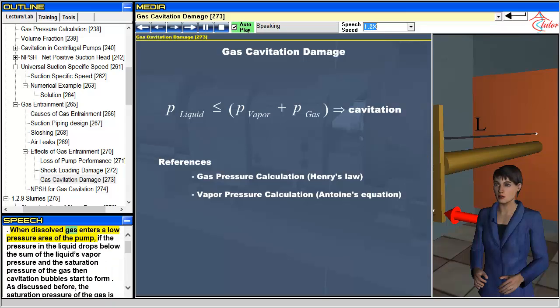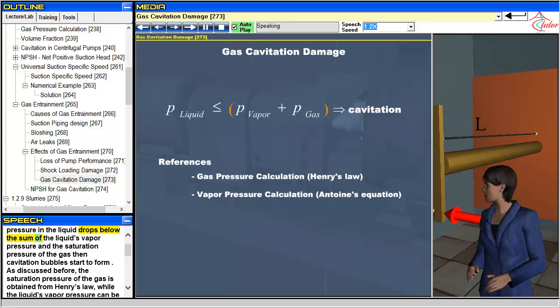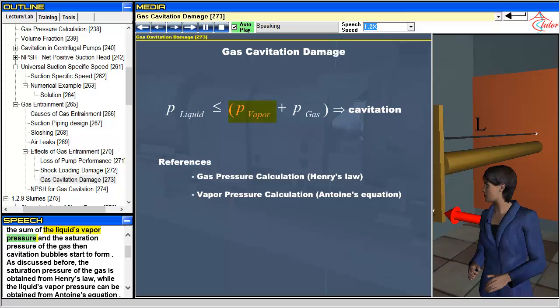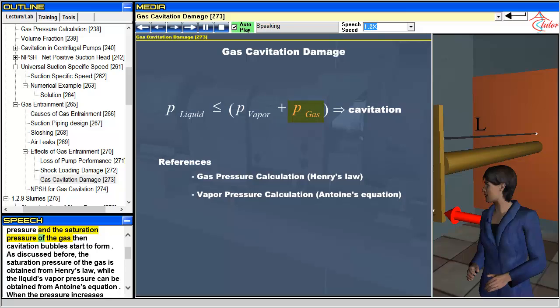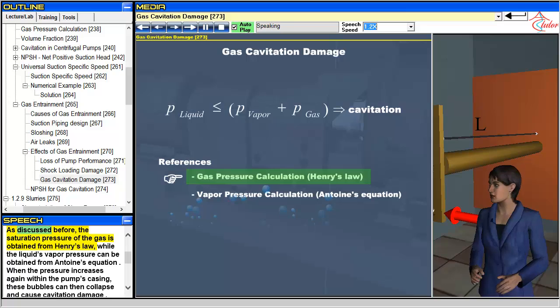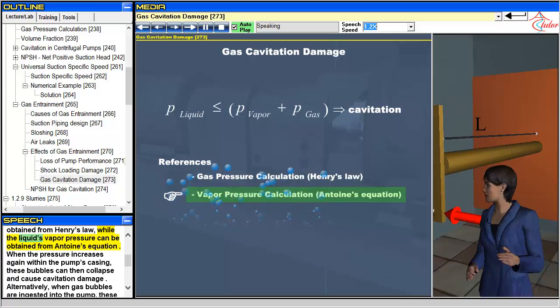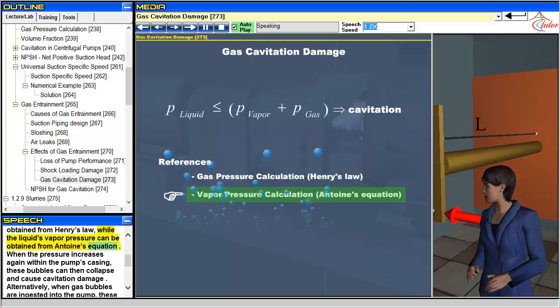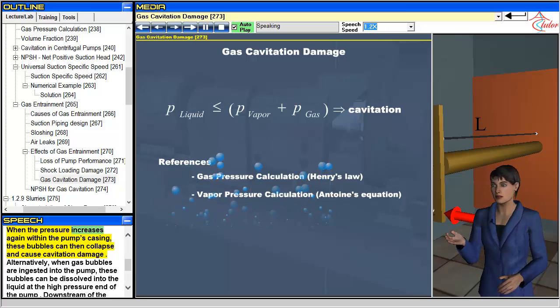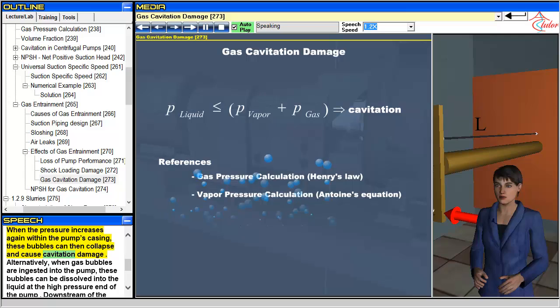When dissolved gas enters a low pressure area of the pump, if the pressure in the liquid drops below the sum of the liquid's vapor pressure and the saturation pressure of the gas, then cavitation bubbles start to form. As discussed before, the saturation pressure of the gas is obtained from Henry's Law, while the liquid's vapor pressure can be obtained from Antoine's equation. When the pressure increases again within the pump's casing, these bubbles can then collapse and cause cavitation damage.